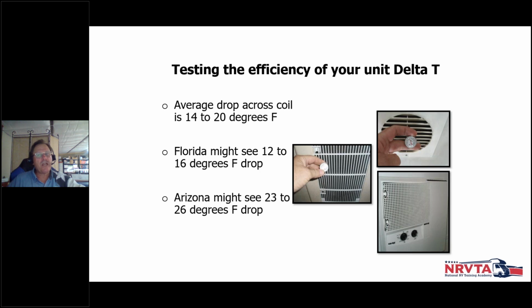This is how we check it, because we do not have the ability to put a set of gauges on it like a refrigeration tech does, since RV air conditioners don't have service ports for us to hook up to. So this is how we check the efficiency. If you're working as a technician, this is how you check it. And if you're doing an RV inspection, this is one of the procedures required for every air conditioner: find out what the delta is, the difference in temperature between what's coming in and what's being discharged.